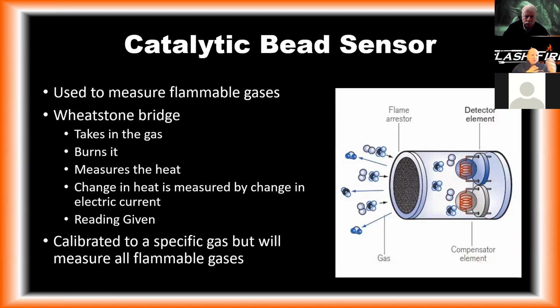The catalytic bead sensor, this is that LEL sensor. It's used to measure flammable gases. It uses what's called the Wheatstone bridge theory. I'll let you read that. Now, this is calibrated to a specific gas, but it will measure all flammable gases. So again, it's very important to remember that as we're walking through and getting a reading on our LEL sensor, while it's only going to be accurate for the gas that it's calibrated to, which is methane, it will read any gas out there. So we have to realize that the readings we're getting on that meter, if it's not methane, are not going to be one for one accurate.